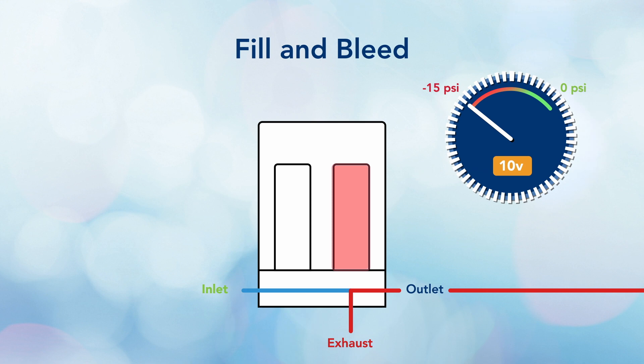If my command changes to reduce the level of downstream vacuum, say from a 10 volt signal to a 5 volt command, the comparator circuit will open up the inlet valve which allows atmosphere into the downstream work area which reduces the level of downstream vacuum to the actual calibrated range.